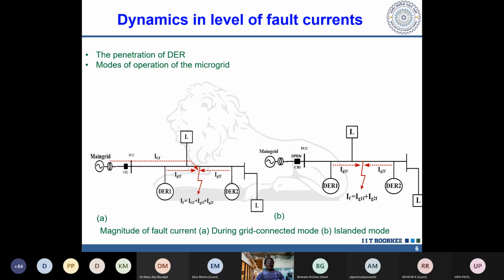So what is the take home, the idea we got from here? That if the AC microgrid is operating in grid connected mode, then the fault current magnitude will be higher, and if it is operating in an islanded mode, then the fault current magnitude will be reduced. This is the conclusion from this. So therefore the dynamics, meaning the change in fault current magnitude, changes from time to time. So that means a fixed setting of the relay you cannot maintain.